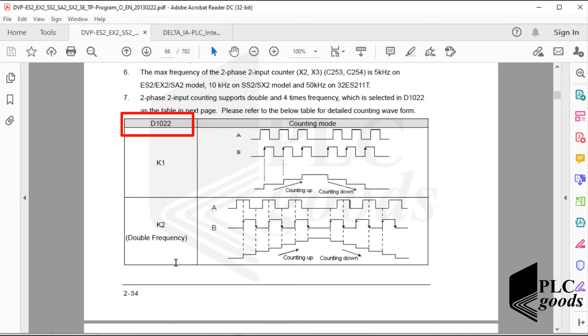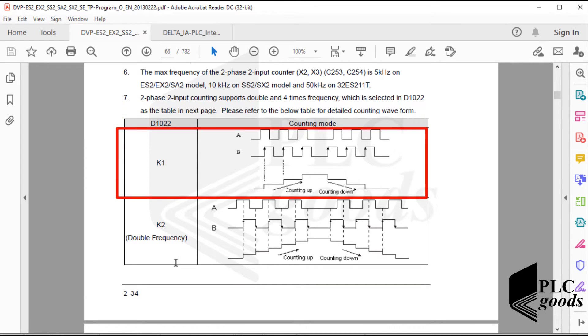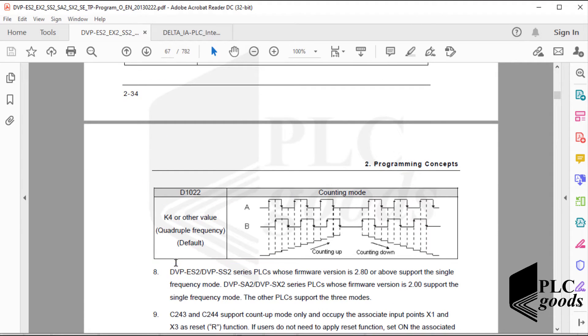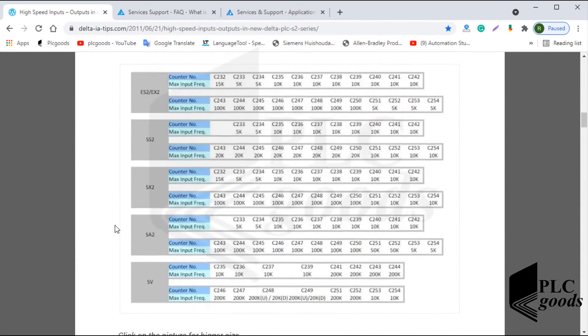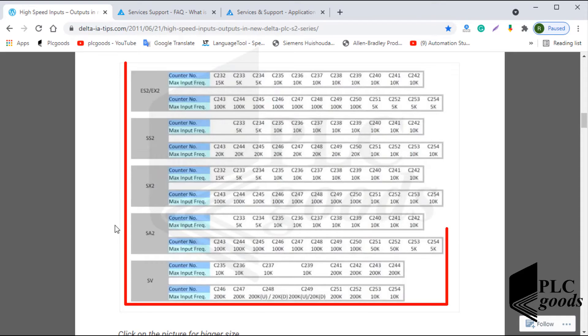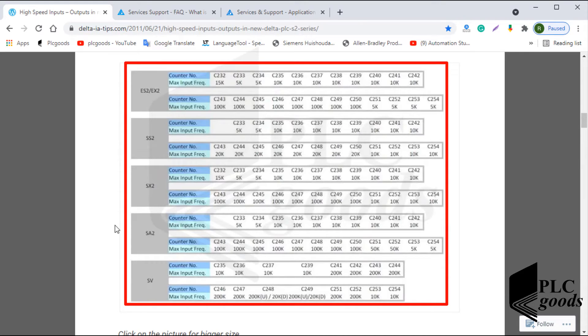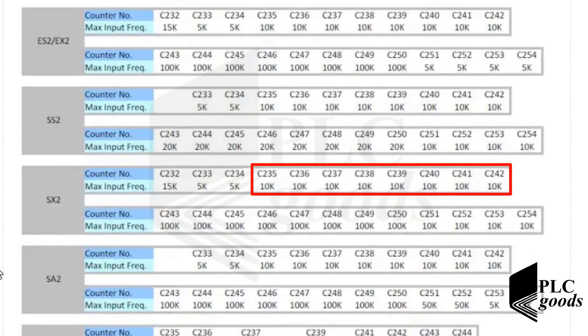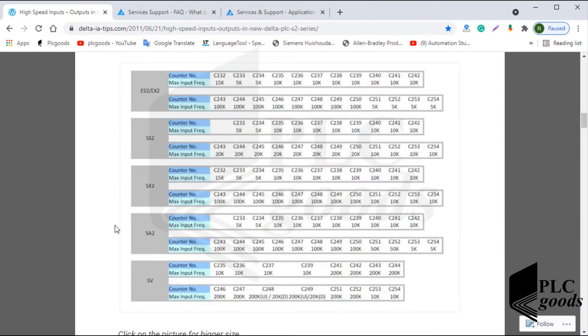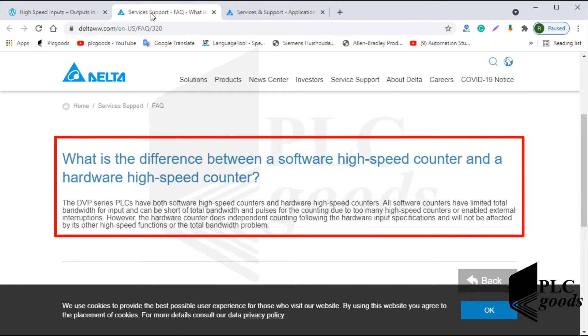Note that the stored number in D1022 is important — whether it is 1, 2, 4, or another number affects counter behavior. My PLC and other DVP series PLCs have both software and hardware high-speed counters. This table displays the maximum input frequency for each counter. For example, depending on the PLC type, these counters can count up to 10,000 signal edges per second, which is enough to count edges produced by most encoders. Note that the maximum input frequency for software high-speed counters decreases if too many high-speed counters are used or if external interruptions are enabled.